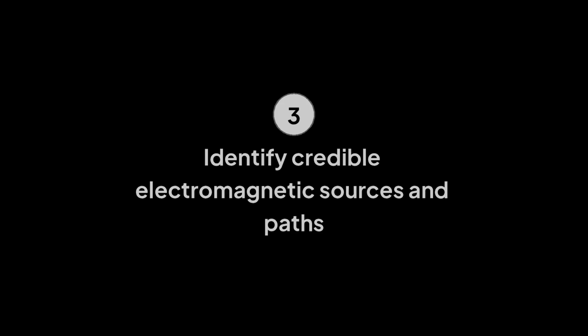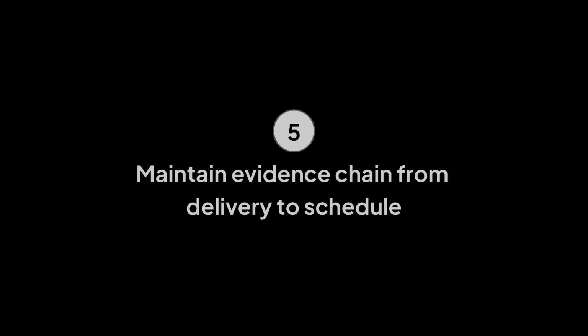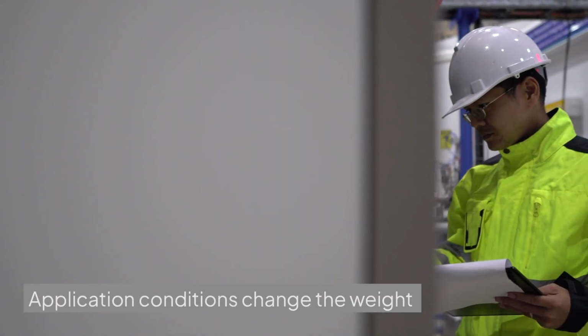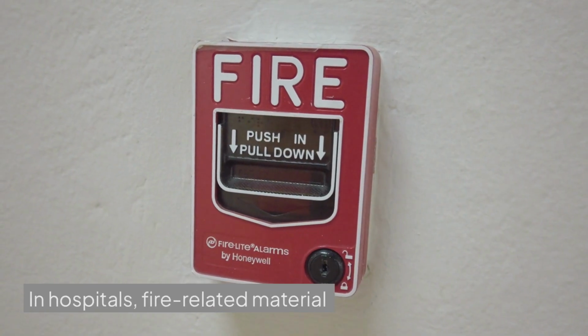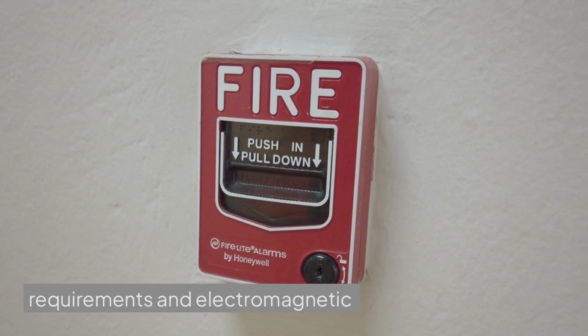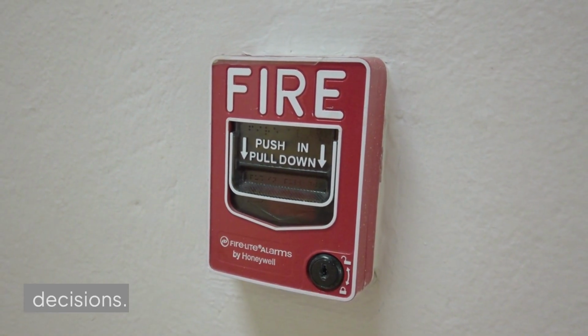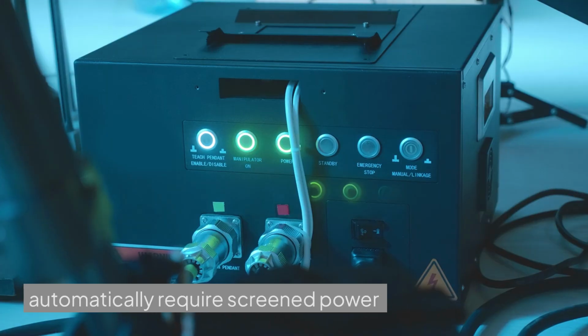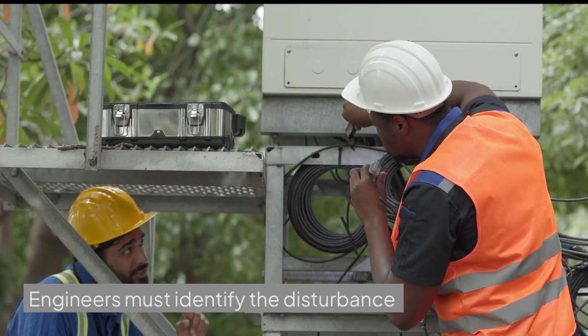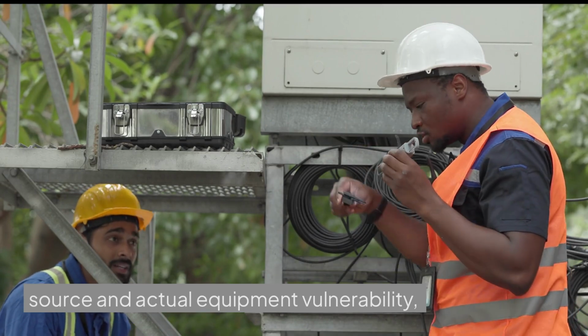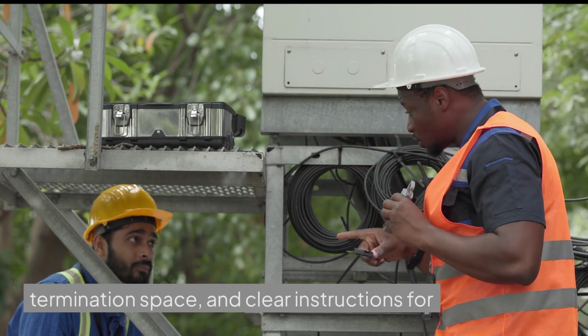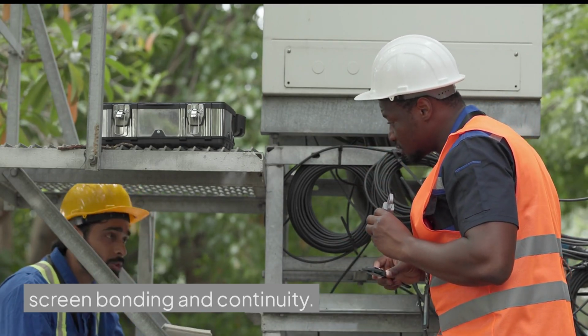Application conditions change the weight of each factor. In hospitals, fire-related material requirements and electromagnetic compatibility must remain distinct decisions. Sensitive equipment nearby does not automatically require screened power cable. Engineers must identify the disturbance source and actual equipment vulnerability, while installers need access, suitable termination space, and clear instructions for screen bonding and continuity.